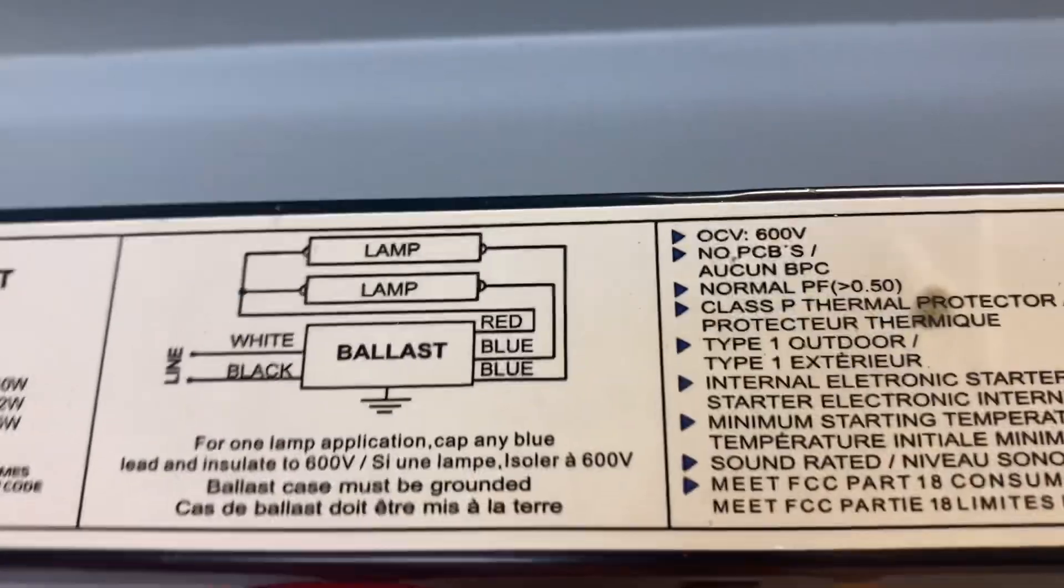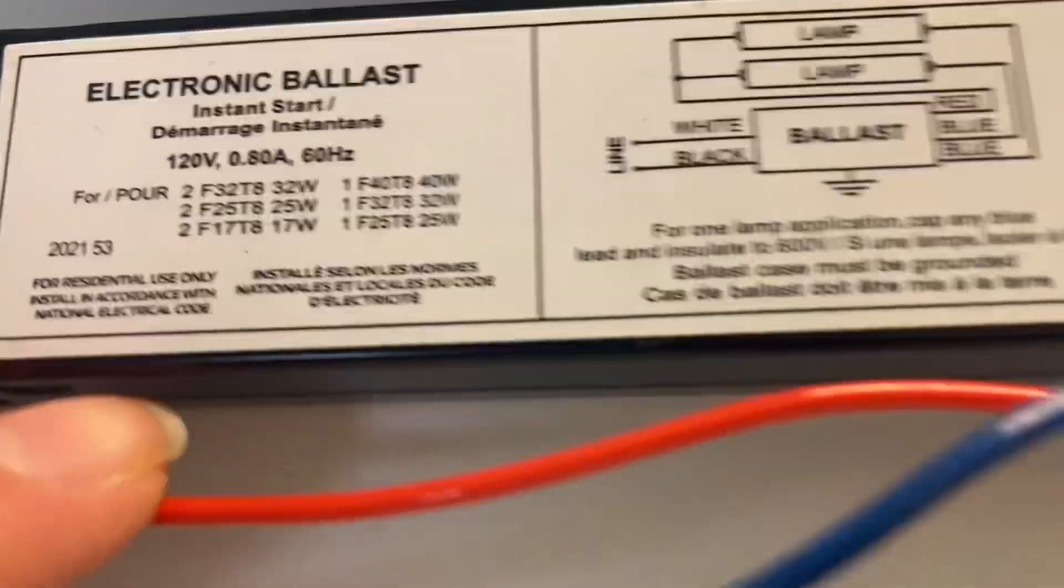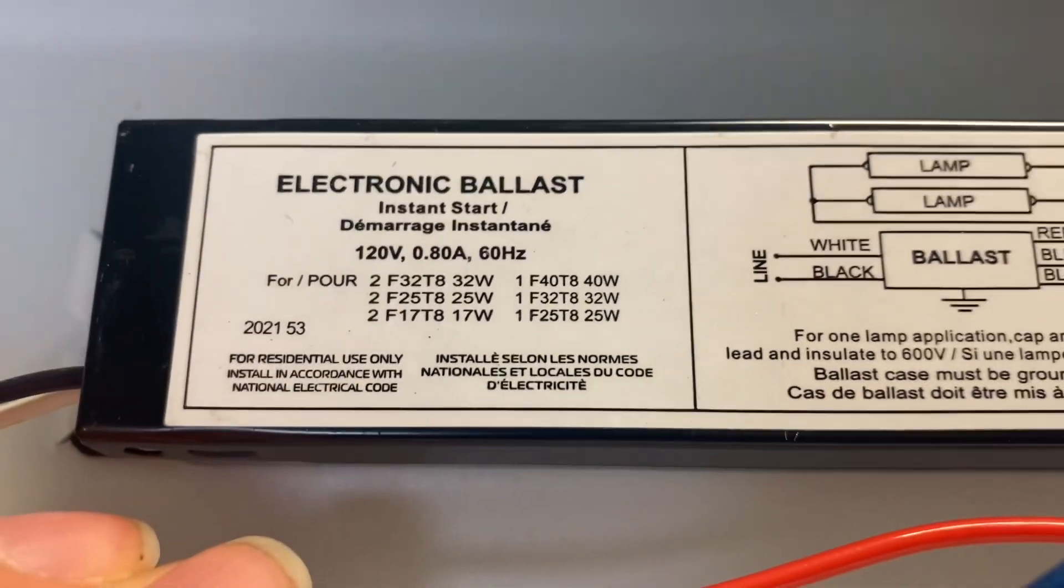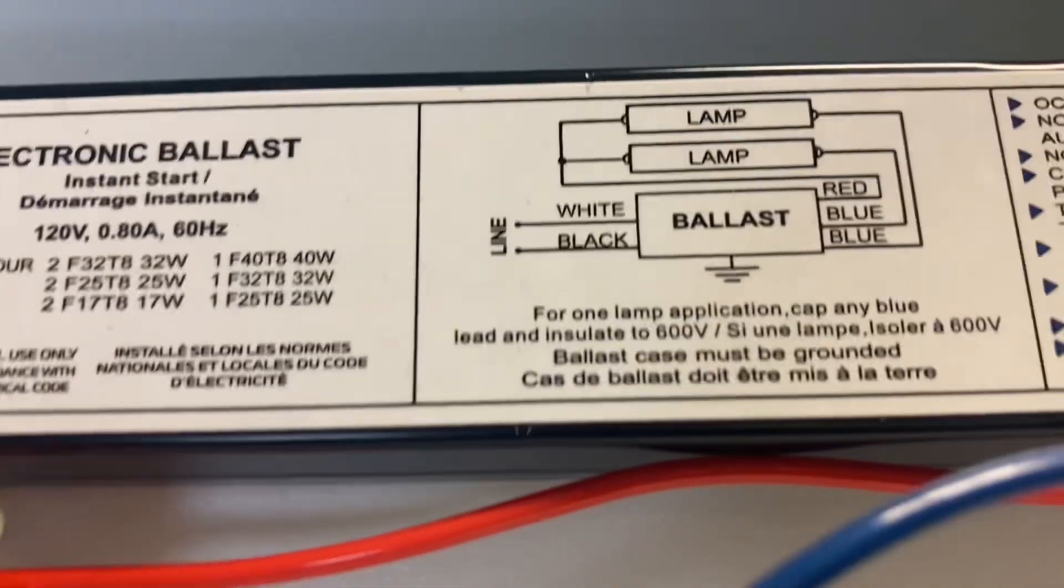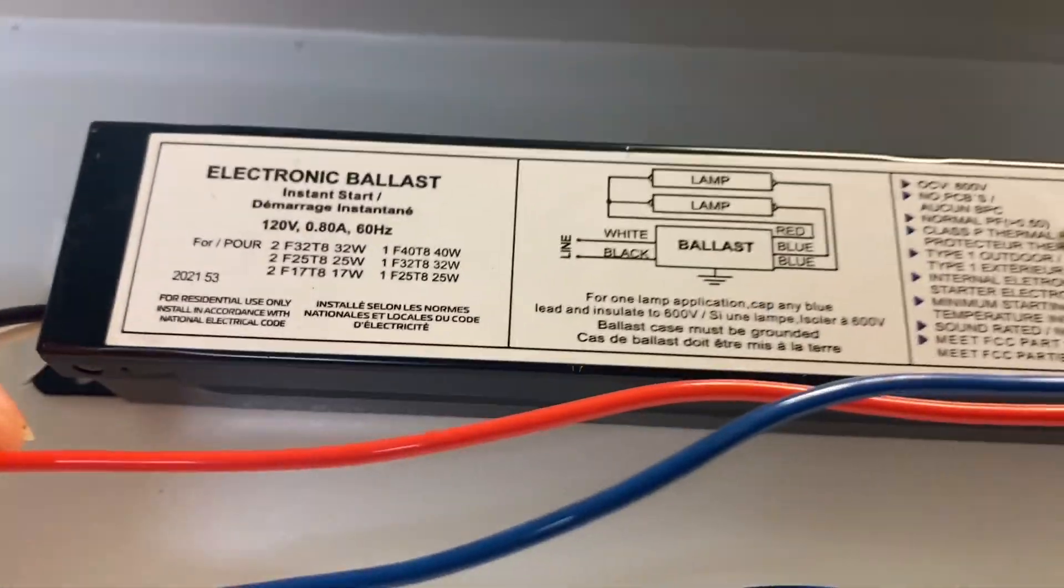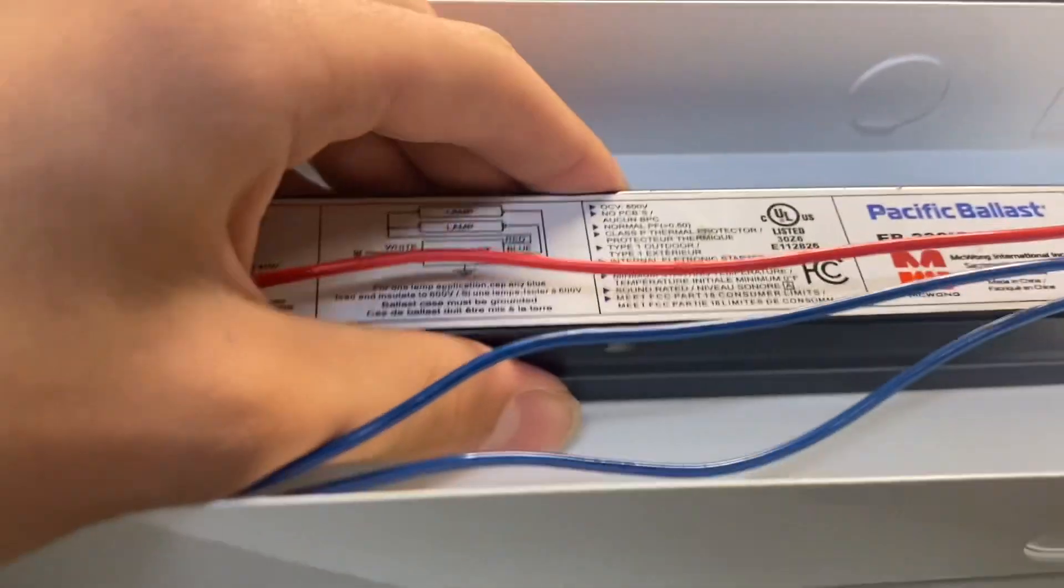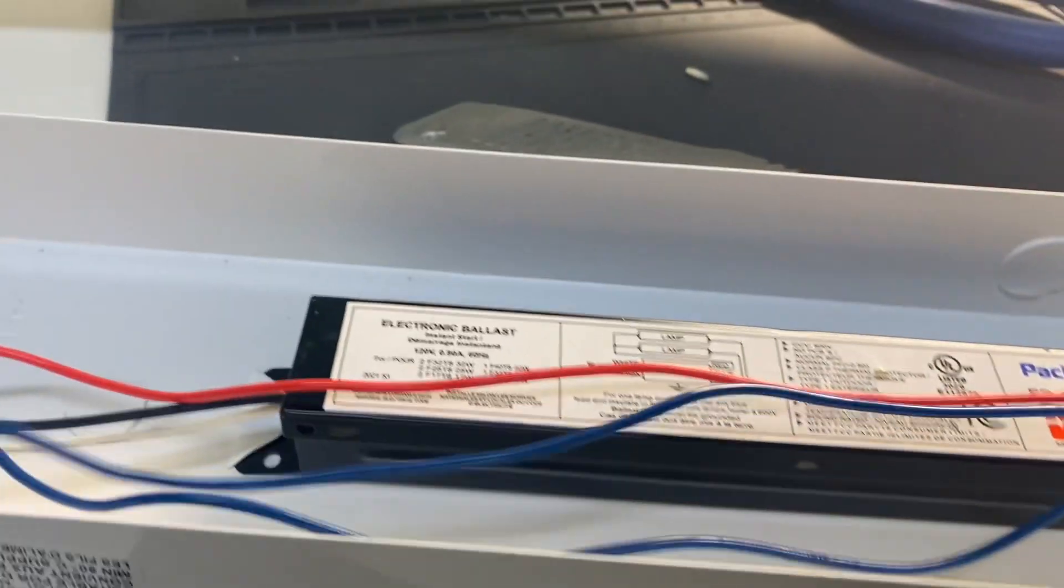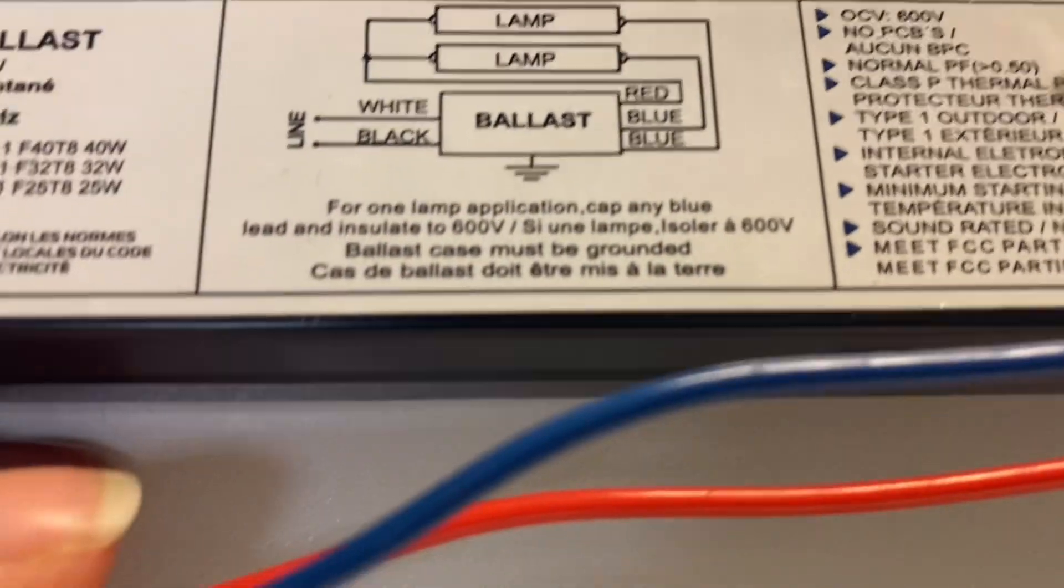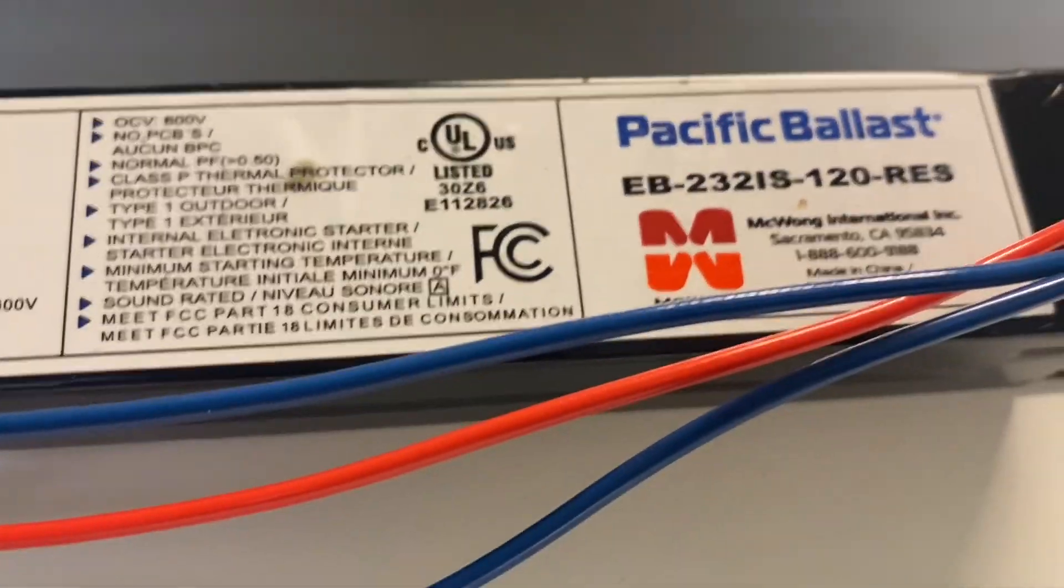So we got a Pacific ballast, very cheap, nasty ballast here. F32 T8, 0.8 amps, instant start, and for residential use only. Normal power factor, so yeah, this is a very terrible ballast. Normal power factor is not something you want, give me a high power factor ballast any day. It has two lamps and a 600 volt open circuit, made in China, of course it is.